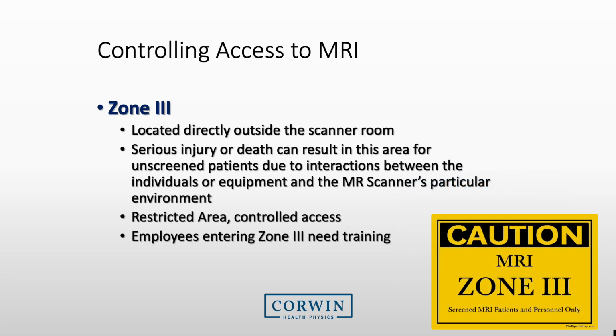Zones 3 and 4 are for individuals that have been trained or are escorted by someone that has been provided adequate training. Zone 3 is an area that is typically located directly outside the scanner room. We usually indicate that serious problems can occur in this area if the wrong equipment or an unscreened patient is present. This area should be restricted, and employees entering Zone 3 need to have MRI safety training.